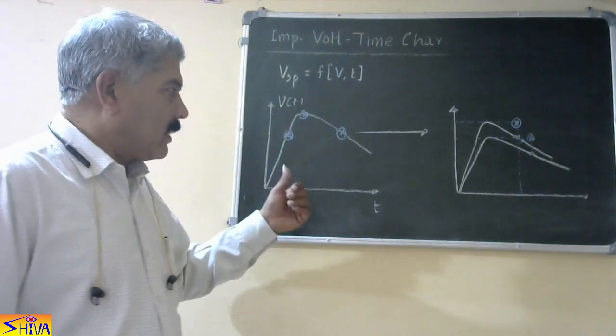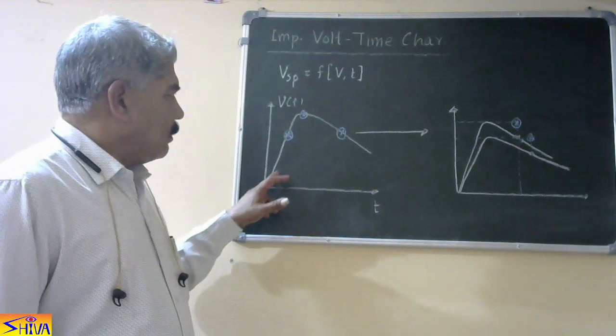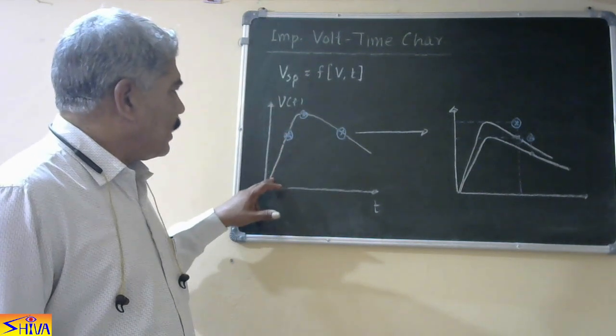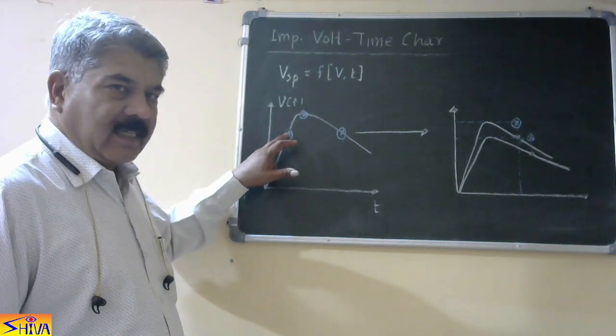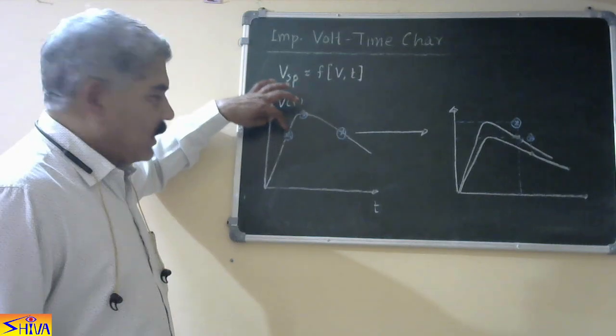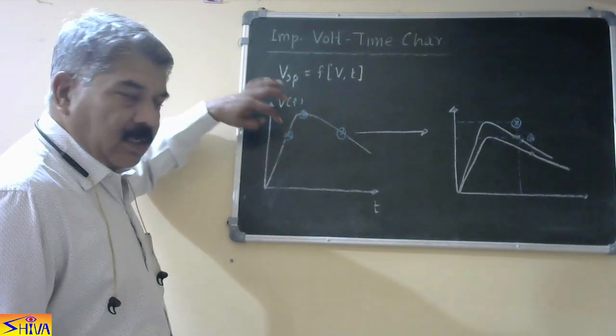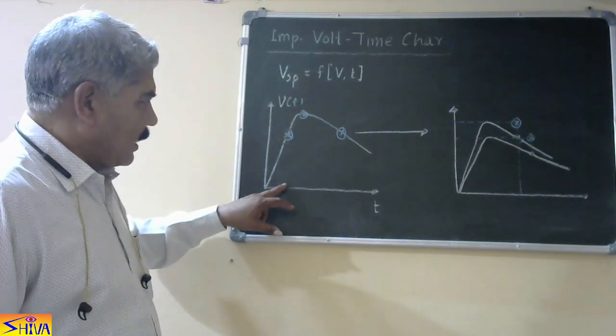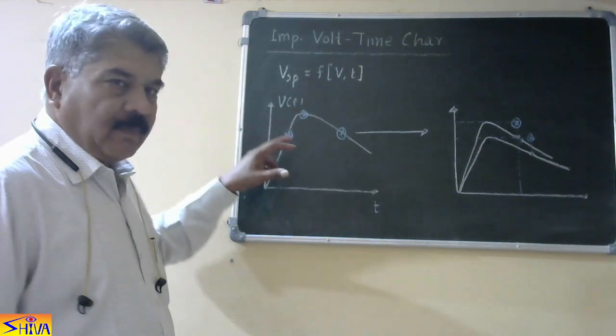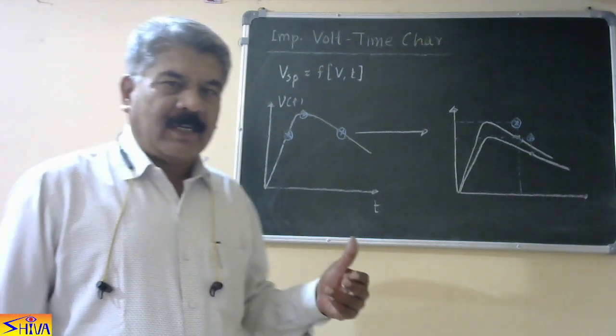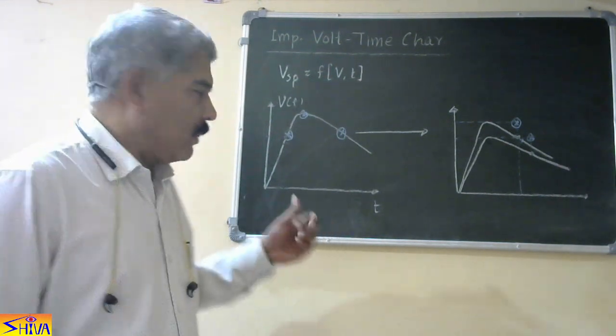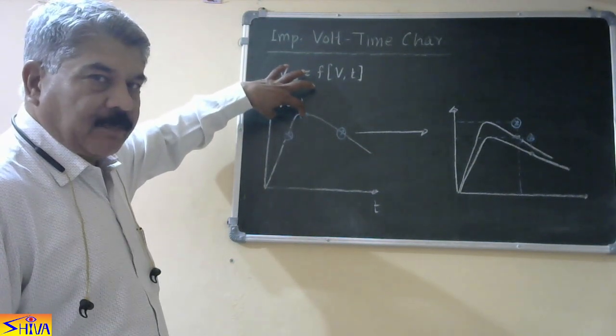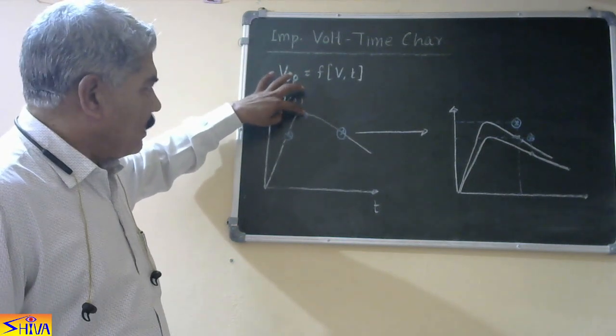Let us see how the points are marked on this characteristic. First possibility: spark over takes place on the rising portion — the wave front. In that case the point of spark over is noted. If spark over takes place at a certain point on the wave front, then on the characteristic that point is plotted. It indicates the insulation sparks over at that peak value — meaning the insulation can sustain that voltage value for that much time. We draw a vertical line to give the time and a horizontal line to give the spark over voltage. Second possibility: spark over occurs at the peak value. When spark over occurs at the peak value, we know that point — this indicates the spark over voltage and the time for which the insulation can sustain.